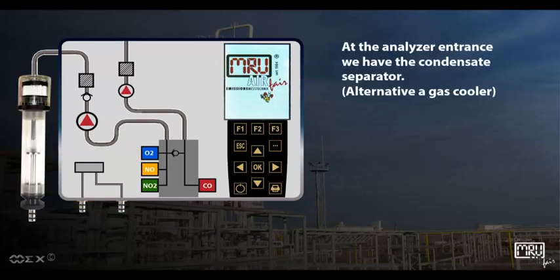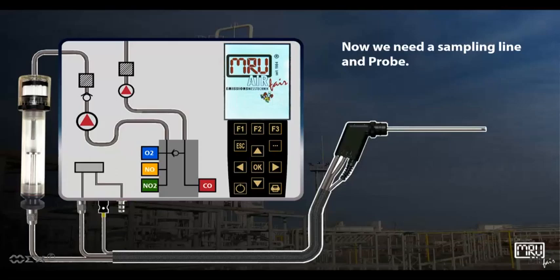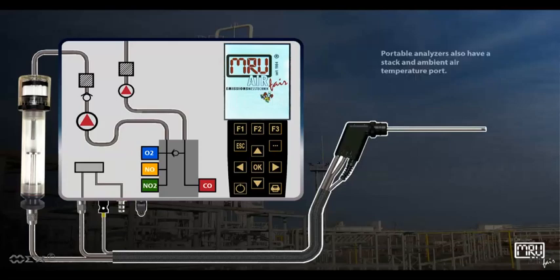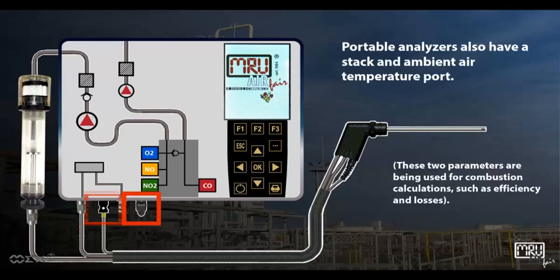At the analyzer entrance we have the condensate separator, or alternatively a gas cooler. We also need a sampling line and probe. Portable analyzers have a stack and ambient air temperature port — these two parameters are used for combustion calculations such as efficiency and losses. Stationary analyzers can have optional stack temperature as well.